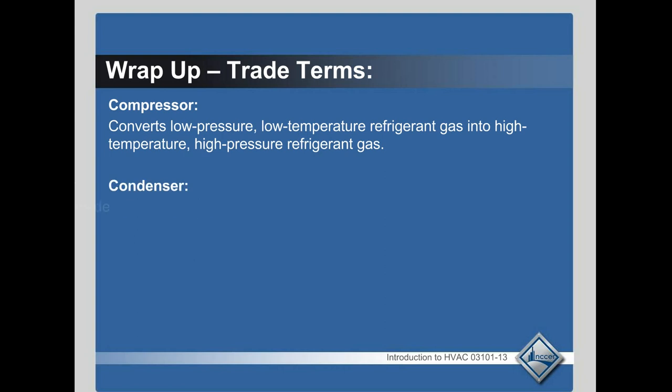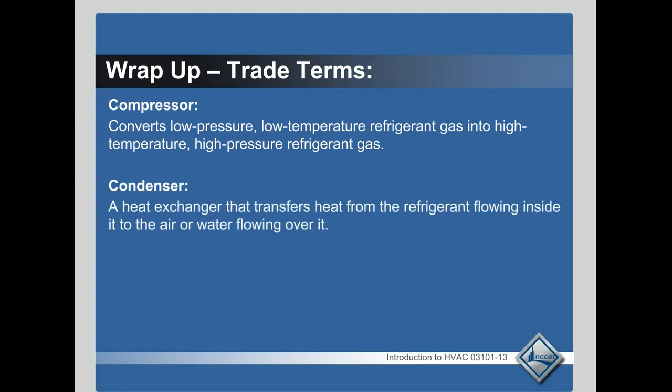The condenser — this is where we reject the heat that we remove from the refrigerator, the cooler, or the house or building. The refrigerant flows through that condenser coil and releases the heat to the outdoor air. Remember, heat flows from a substance with more heat — with molecules in motion — to a substance with less heat. So that refrigerant is heated up by the compressor and the heat is removed from the refrigerant to the outdoor air inside the condenser. It also changes the refrigerant back down to liquid from vapor.